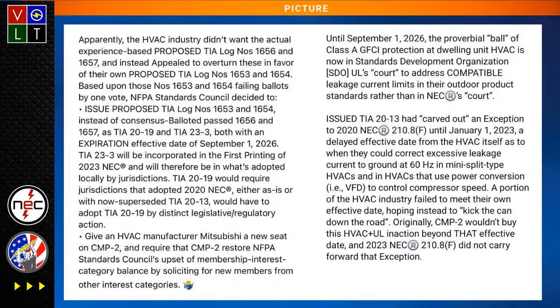Do you really think that a VFD leaking current on the equipment ground is a hazard if the equipment ground's solid and installed correctly and inspected and everything's good? Do you really think it's a really big hazard for an HVAC unit to have a VFD that's leaking current onto the equipment ground if everything's installed correctly? No. So that's where we're coming from.